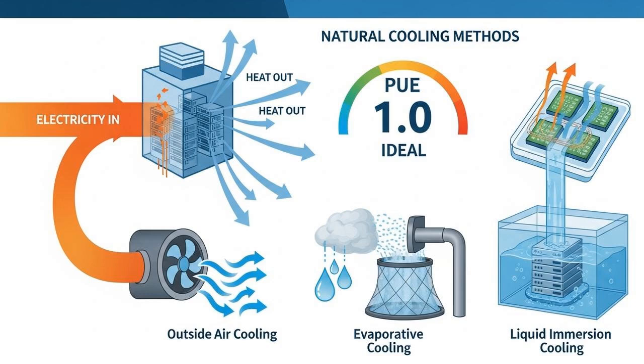Over the years, we've gotten smarter. We learned that keeping data centers at freezing temperatures was incredibly inefficient. New guidelines allow them to run hotter, saving energy. We've developed clever techniques like using outside air in cool climates, or evaporating water to cool the air. And as processors get even hotter, we're seeing more liquid cooling, piping liquid directly to the chips, or even submerging entire servers in a non-conductive fluid.